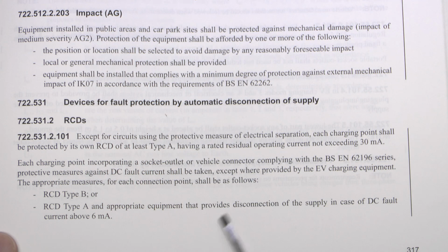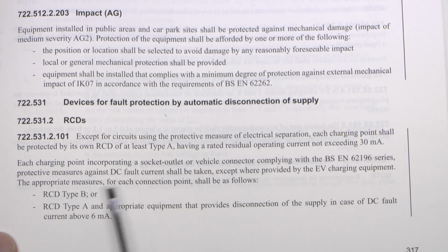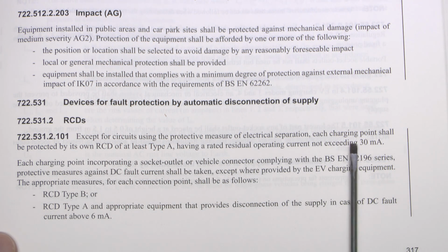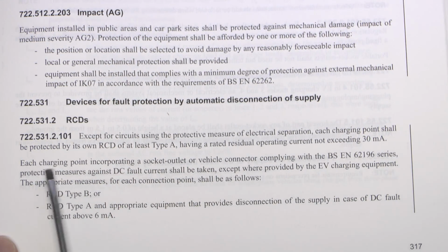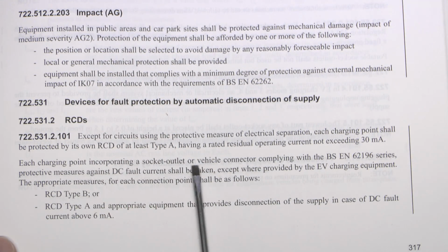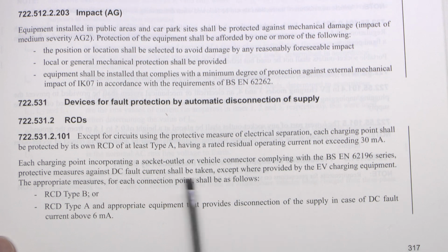This has been expanded quite considerably, and it now actually specifies some very specific types of RCDs you can use. So except for circuits using the protective measure of electrical separation, which is uncommon, each charging point shall be protected by its own RCD of at least type A, and the rated current not exceeding 30 milliamps. And each charging point incorporating socket outlet or vehicle connector, complying with these standards here.